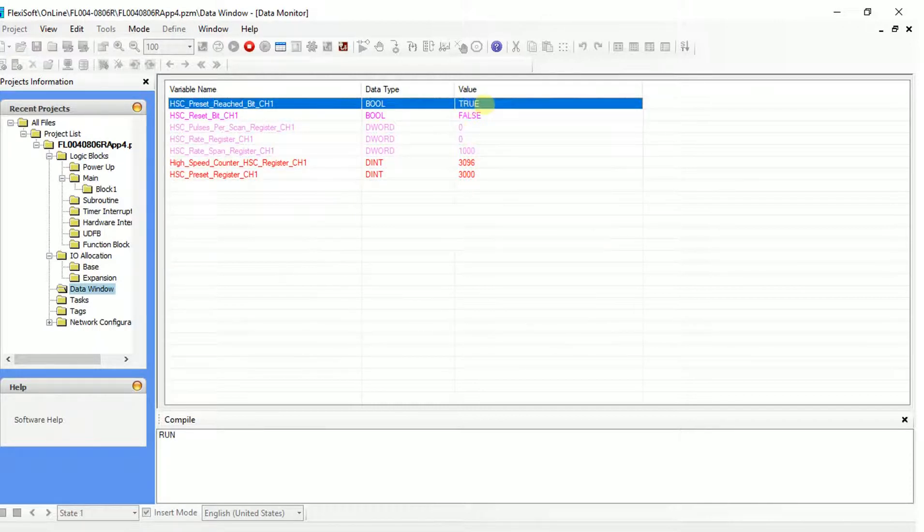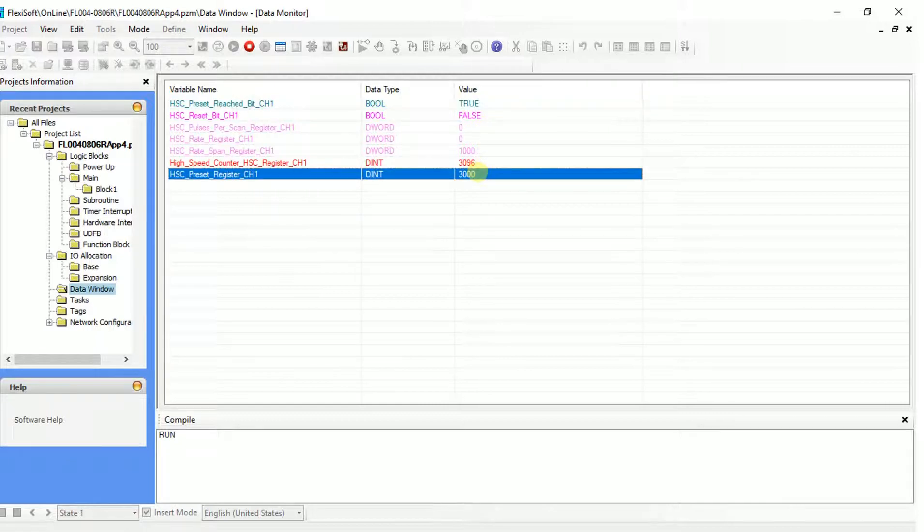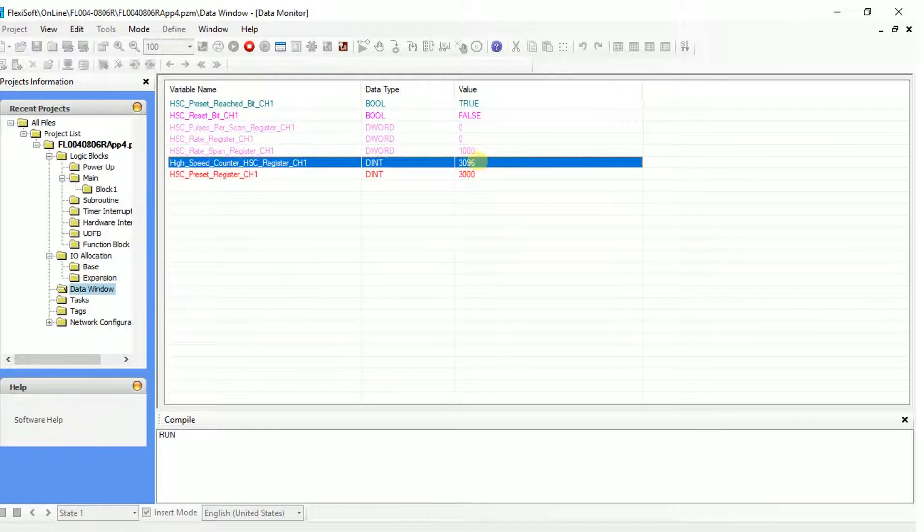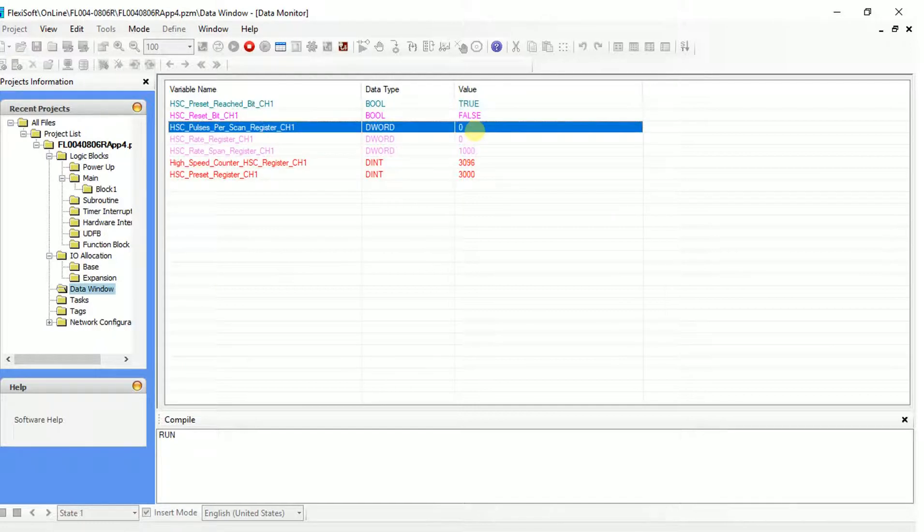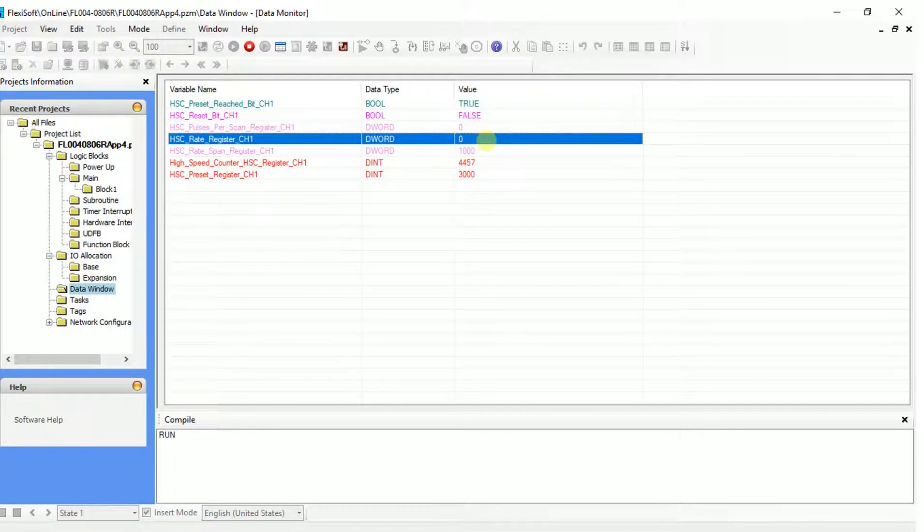We see that the HSC preset bit gets set when the encoder reaches the preset value of 3000. Here it shows number of pulses counted within the time that was defined. Here it is set to 1 second. This shows frequency of pulses in hertz.